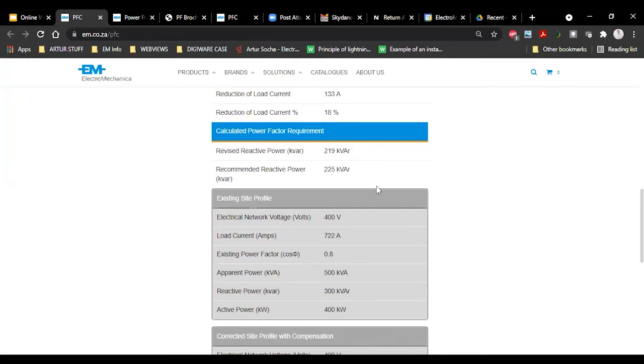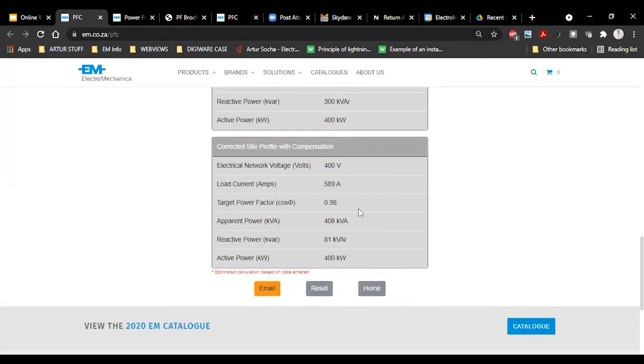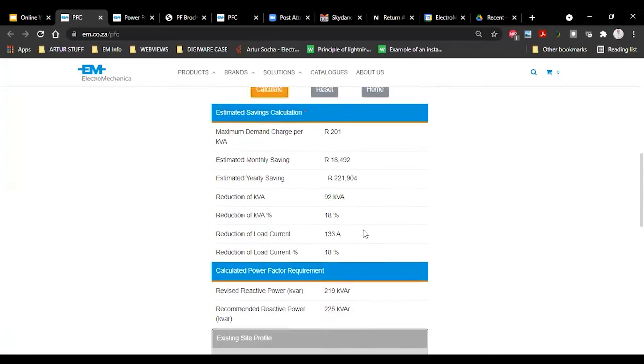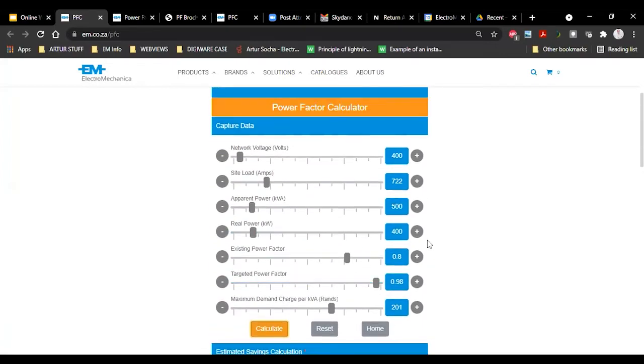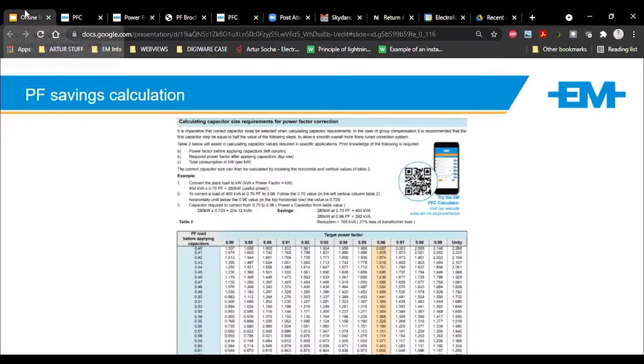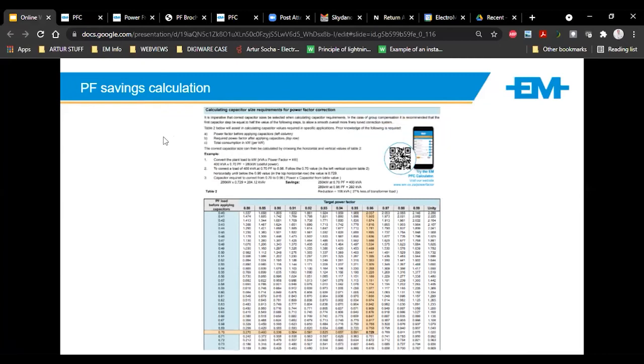So this calculator is free to use, and you can email the results to yourself. Again, the important bit is the actual data you capture. You need this information to start. If a guy gives you a whole lot of motors all over his site, you're going to drastically oversize the system. It would be better to do a bit of measurement for a couple of days and say, okay, that is what you need at the point of coupling. So that's just a basic savings calculation.